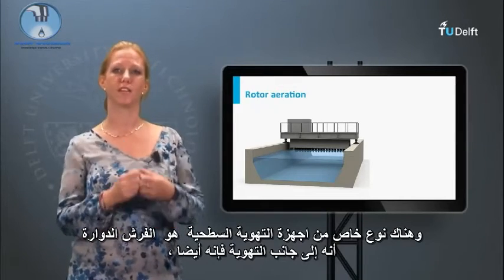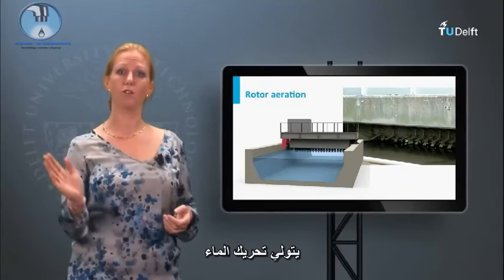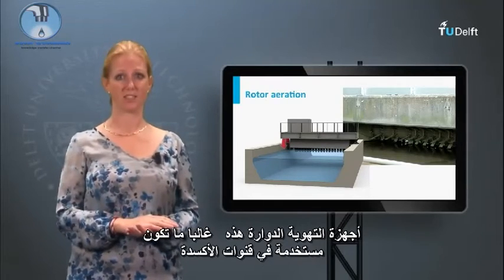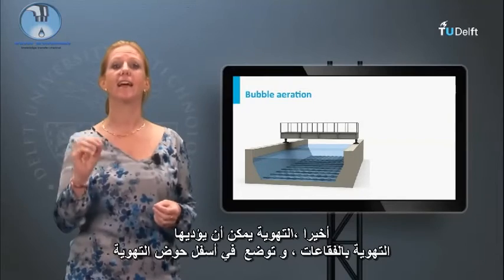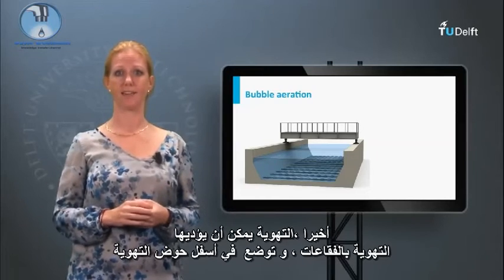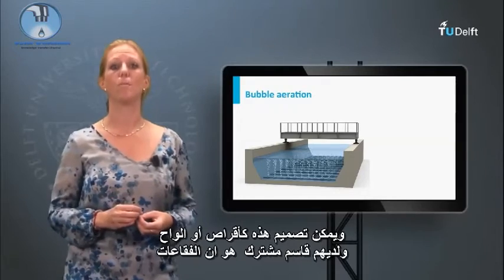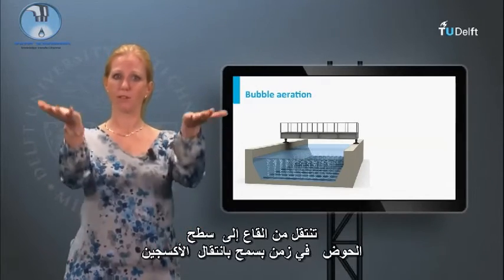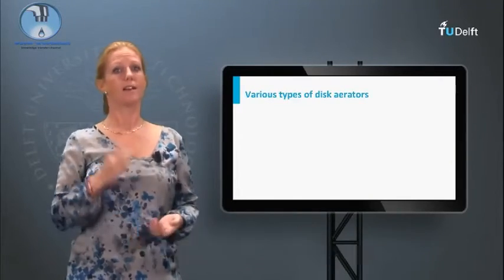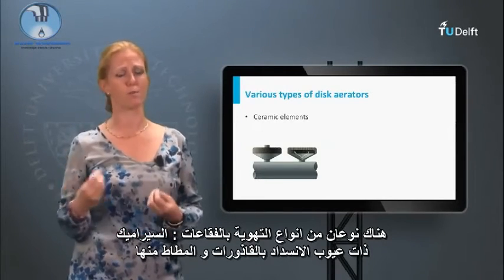A special kind of surface aerator is the rotor aerator, which besides aeration also takes care of the motion of the water. These rotor aerators are often used in oxidation ditches. Aeration can also be performed with bubble aeration placed at the bottom of the aeration tank. These can be designed as discs or plates, and fine bubbles travel from the bottom to the surface of the tank, which generates time for oxygen transfer. There are two types of bubble aerators: ceramic ones with the drawback of fouling, and rubber ones.